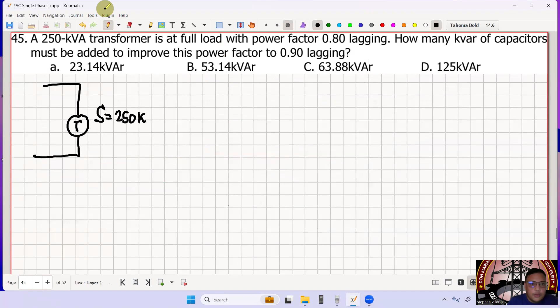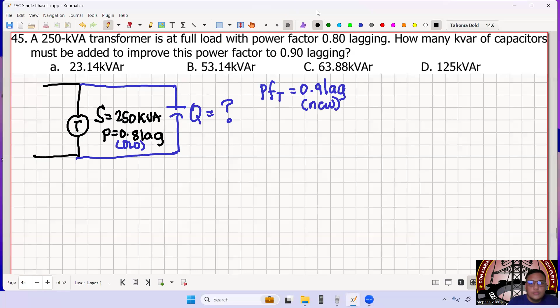So what capacitor do we add, the kVAR of the capacitor or the Q, so that our overall power factor will be 0.9 lag. This is the old power factor. So let's get the Q here. Q cap is equal to P load multiplied by tangent theta old minus tangent theta new.